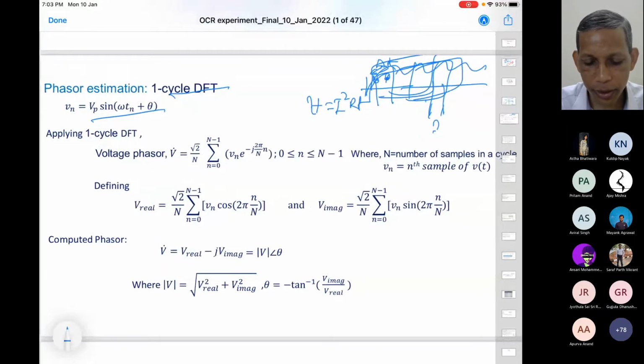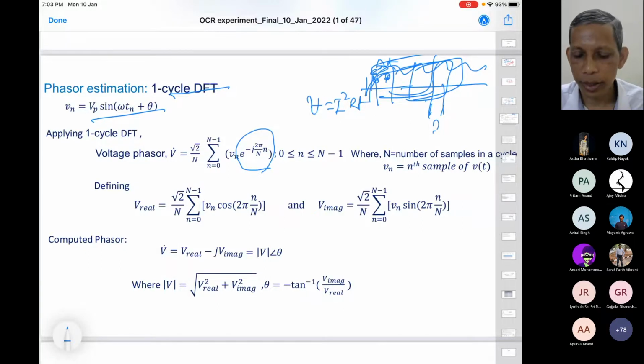So now the point here is that for the voltage phasors, we have a Fourier coefficient e to the power minus j 2 pi n by N. Capital N is the number of samples in one cycle, and small n is every sample 1, 2, 3, 4, up to 7, 8, whatever samples are in that one cycle window. This is the Vn, the samples 0, 1, 2, 3, up to 7. In case N is 8, there will be 8 samples, 0 to 7. Each sample is multiplied with a particular Fourier coefficient like this.